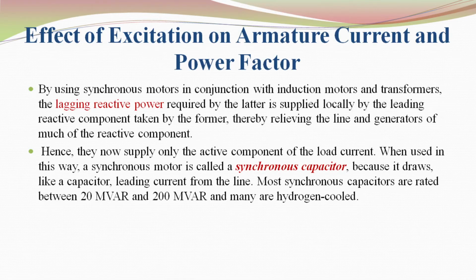So by using synchronous motors in conjunction with induction motors and transformers, the lagging reactive power which is required by the transformers and the induction motors is supplied locally by the leading reactive component taken care of by the synchronous motors. Thereby relieving the line and generators of much of the reactive component. So they now supply only the active component of load current. When used in this way, the synchronous motor is called a synchronous capacitor.